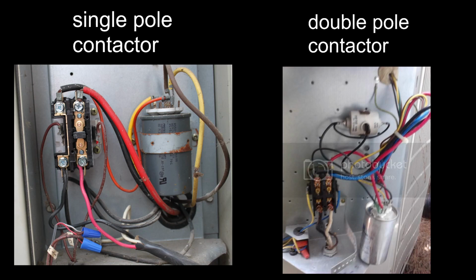If you look at a single pole contactor, you will see a red and black wire coming in. Well, that's the direct feed from the home. It means it's coming from a disconnect box, and it feeds on one side of the contactor on the bottom. And then on the top side is where the connecting wires or voltage wires from your compressor and your condenser fan motor are fed over. And it is red and black as well.